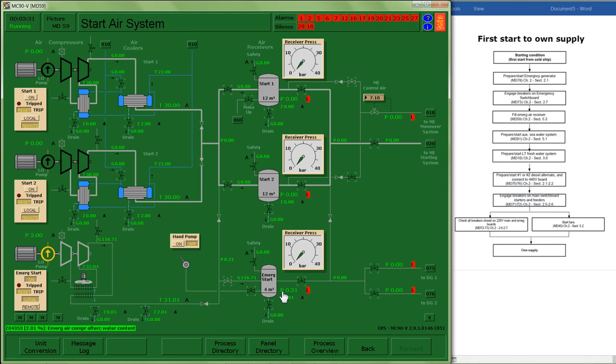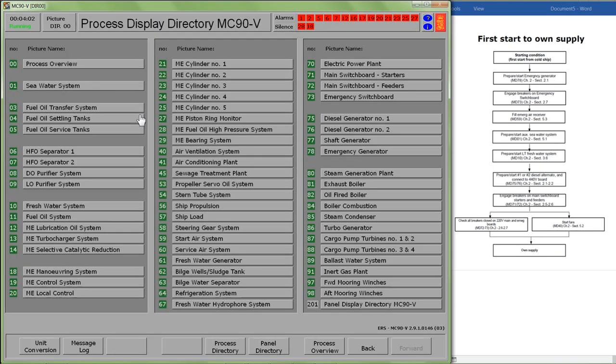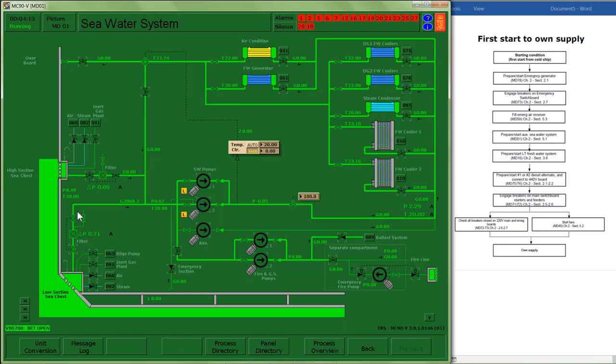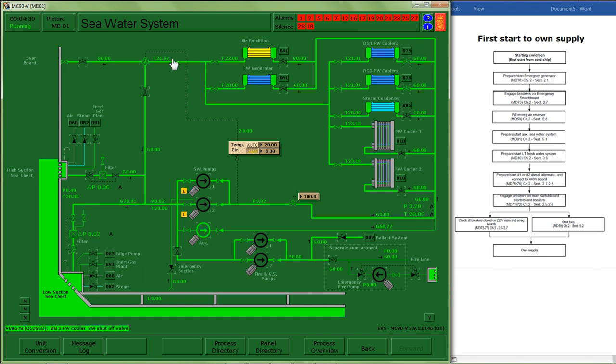My next step: prepare and start the auxiliary seawater system MD01. So I have two places where I can draw raw water in from. I'll choose the low suction. I have an auxiliary pump. I'm going to feed water through my diesel generator coolers. And I'll have an overflow valve as well as a recirculation valve. So I've started up my water system.